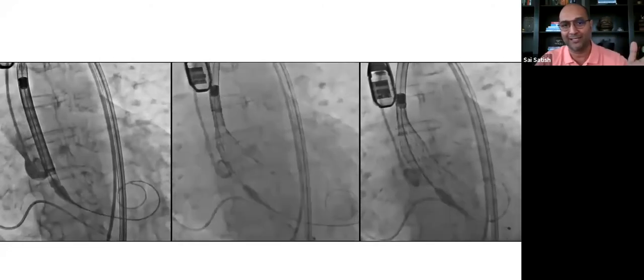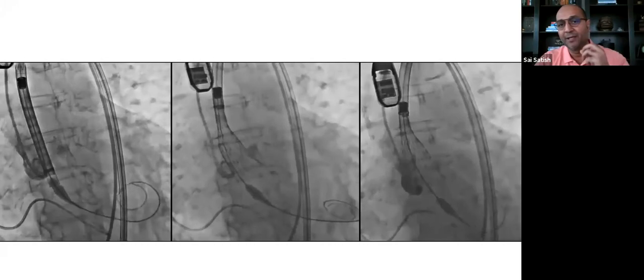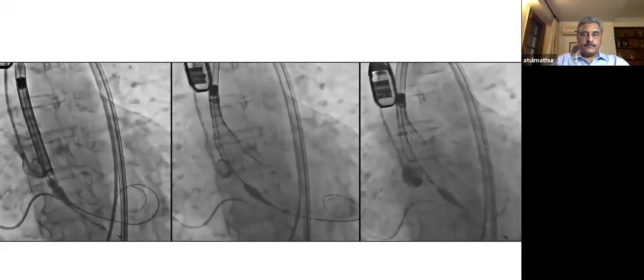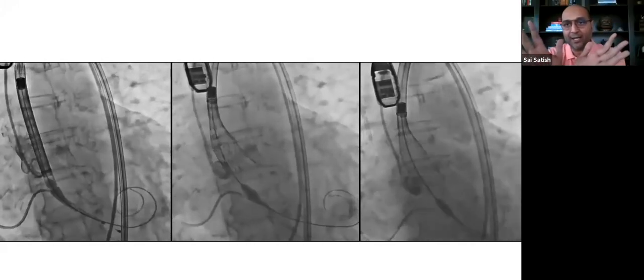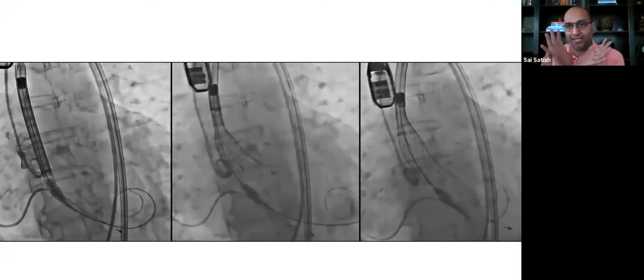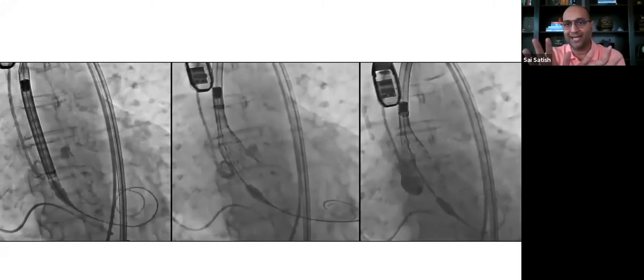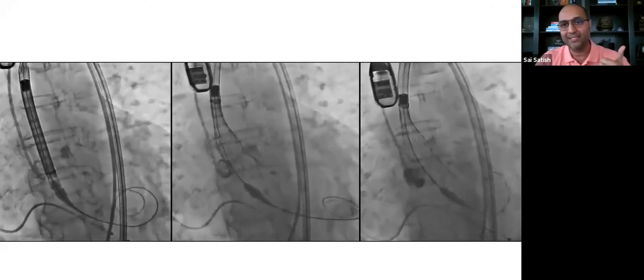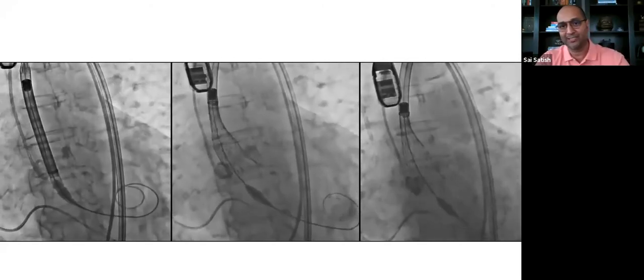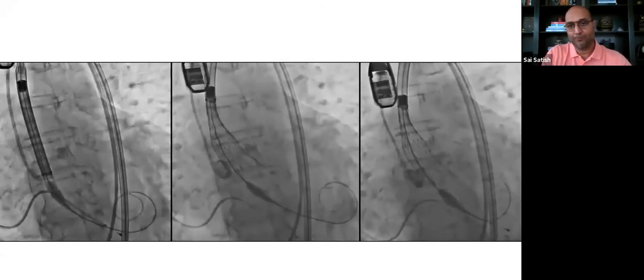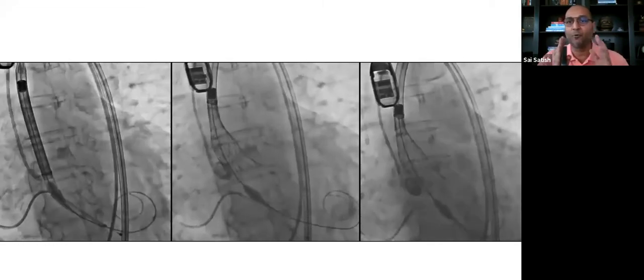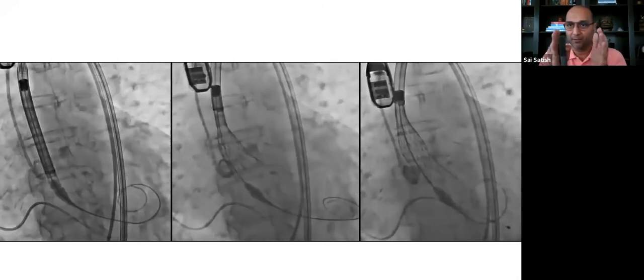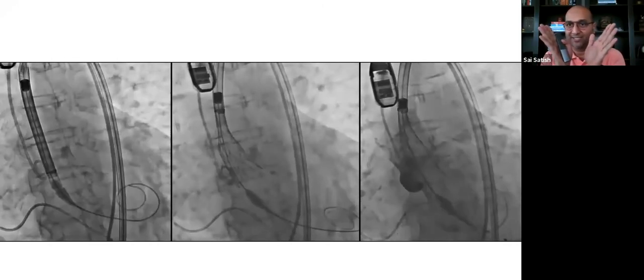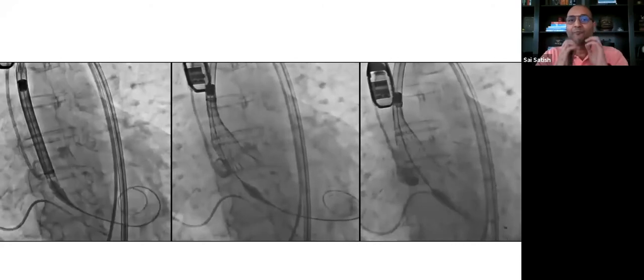I don't worry about the coaxiality. As I start opening the valve, till it reaches the annulus, the 34 opens like an alligator, catching the entire cardiac output, especially in a normal heart, and tends to bounce up and down. To minimize that, you can either pace and cut cardiac output, or do what I'm doing in this image, gently pushing the wire against the LV to stabilize the valve at the depth I like until I make annular contact. Keep in mind the 34, unlike the other three valves, is not tapered parallel. It still retains the core valve design that's tapered out, and has a huge tensile force, so it does tend to dive.